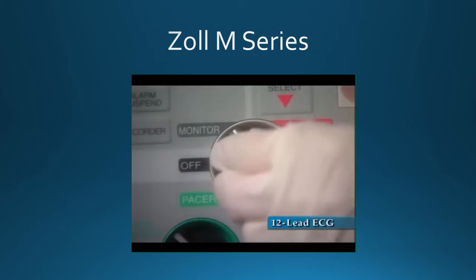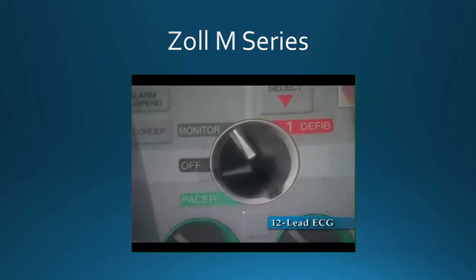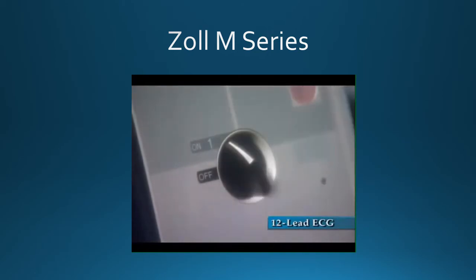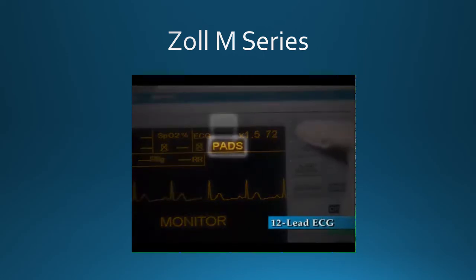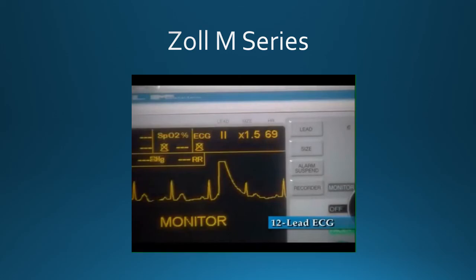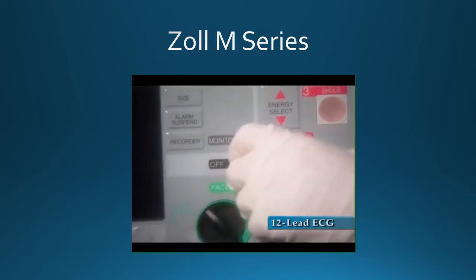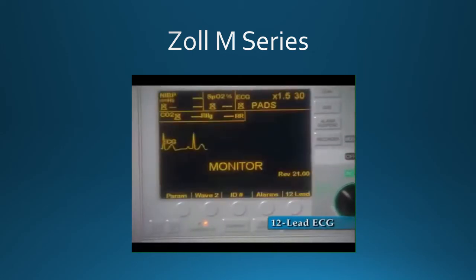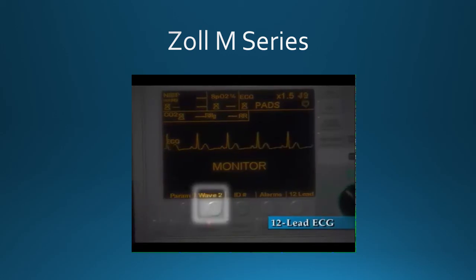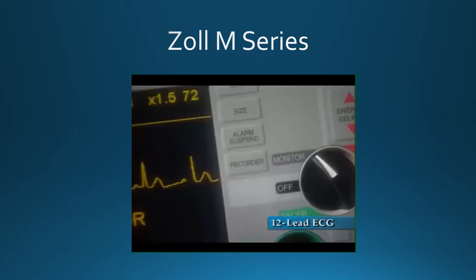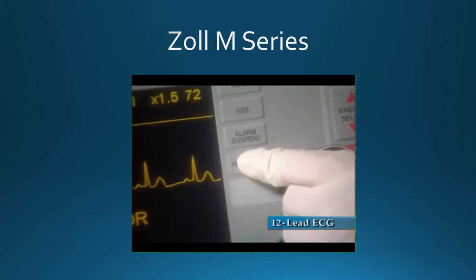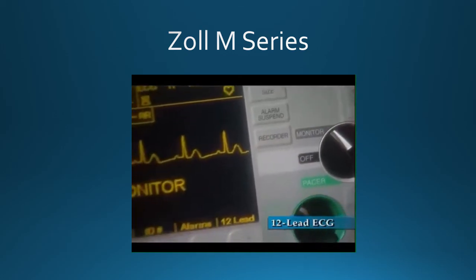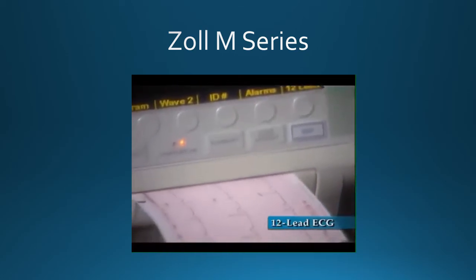On manual M-Series defibrillators, turn the selector switch to monitor. On M-Series with AED, the switch should be turned to the on position. If pads or paddles are selected, select one of the leads. When the M-Series is equipped with 12-lead capabilities and the selector switch is turned to monitor, the physiological monitoring menu will be displayed with the following soft keys: parameter, wave 2, ID number, alarms, and 12-lead. To rapidly acquire a 12-lead, press and hold the recorder button for 3 seconds. A 4x3 12-lead report without interpretation will be printed.